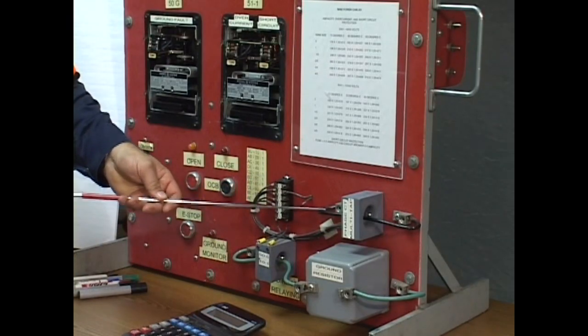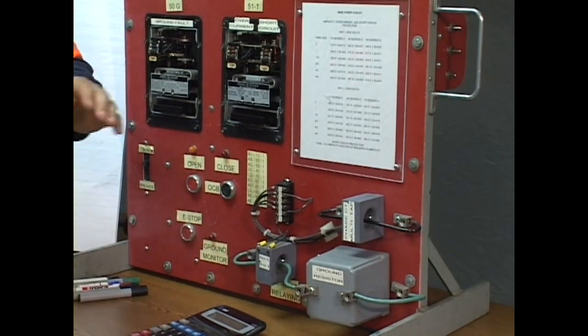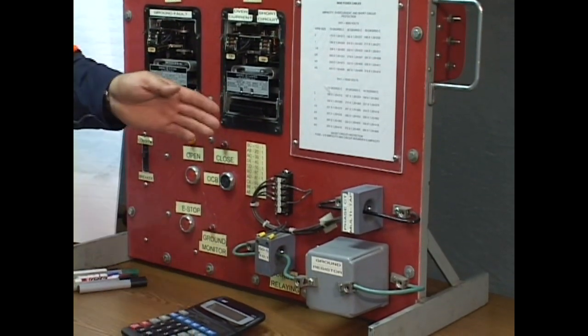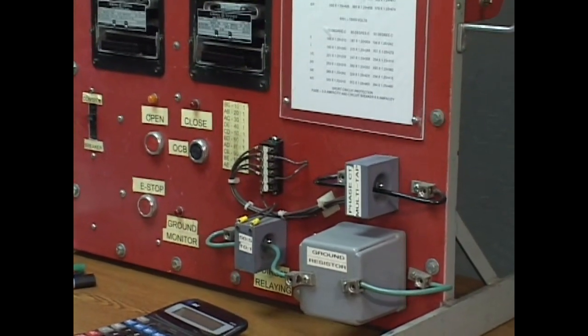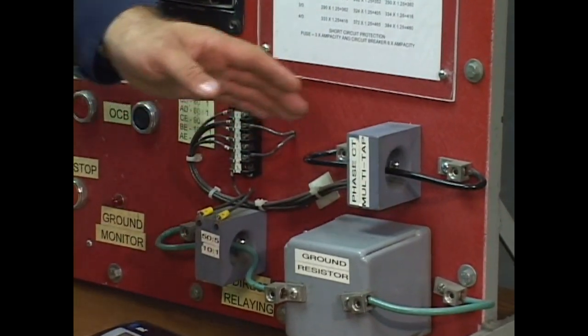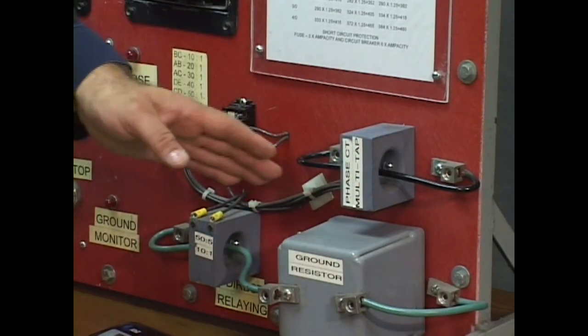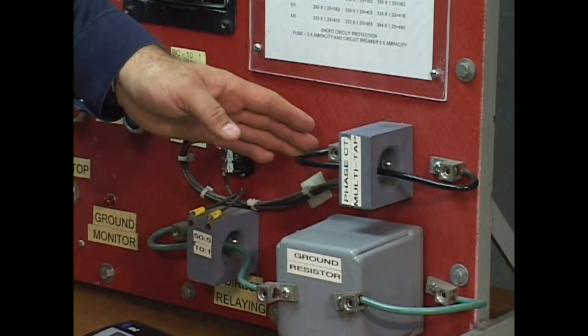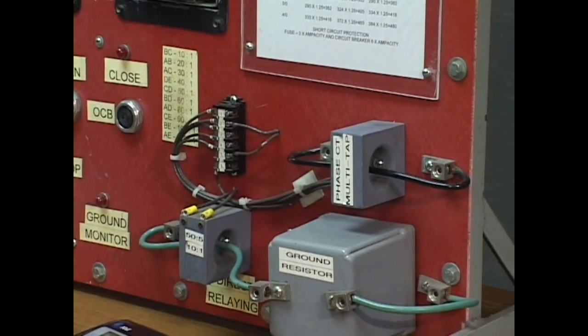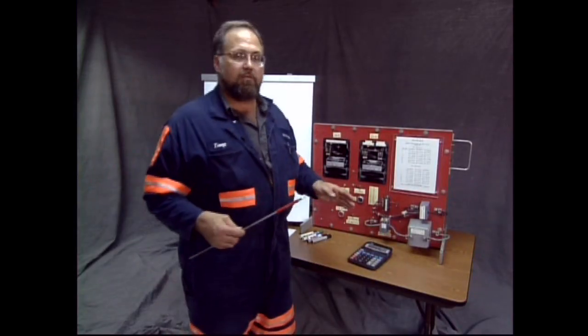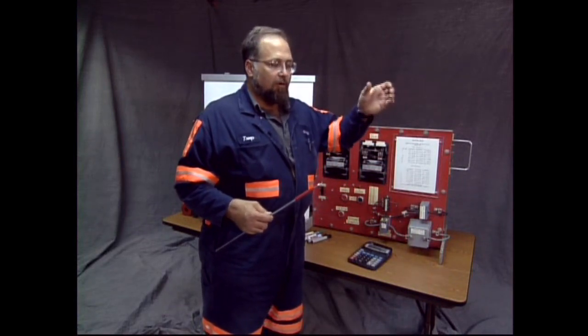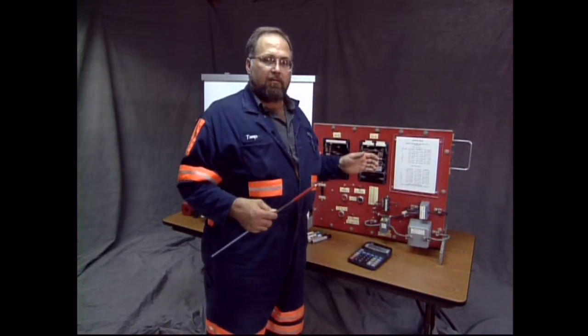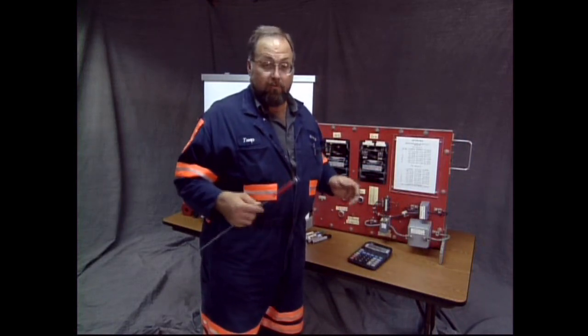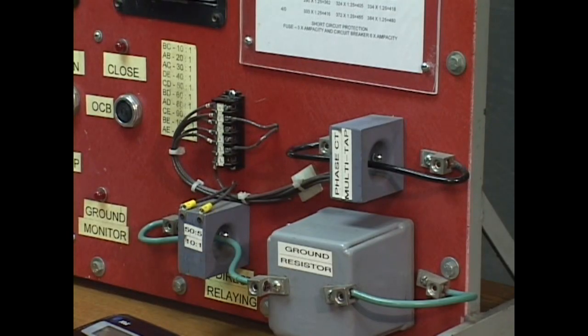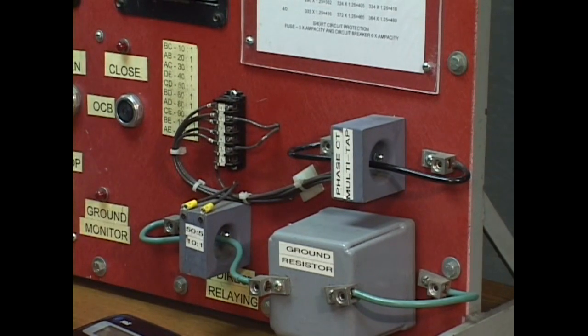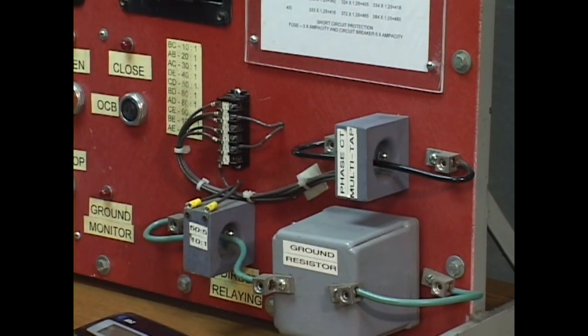The primary of this transformer is the phase wire or the conductor that passes through the window. Some of them have a bar type CT where you bolt a phase wire on one side, it doesn't actually move through this, and you bolt the phase to the other side. Or there could be a hub type CT where cable entering this enclosure passes through a hub, through this CT. But the conductor that passes through the window is the primary. The winding of the CT is the secondary. The CT has an ampacity for the secondary of 5 amps.